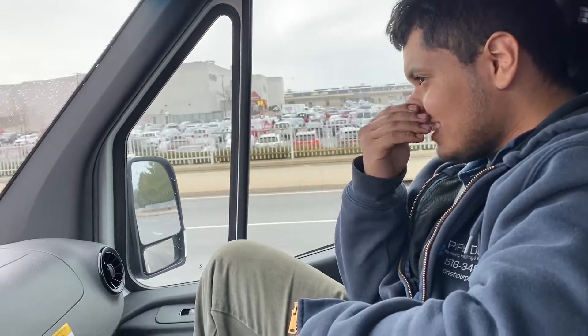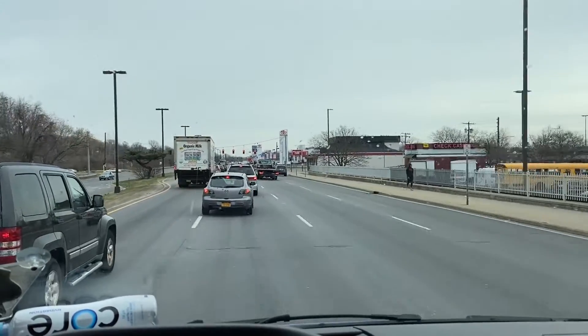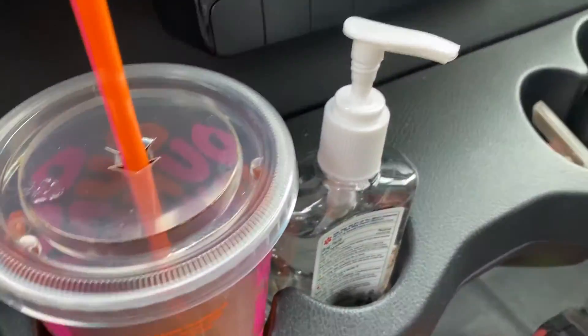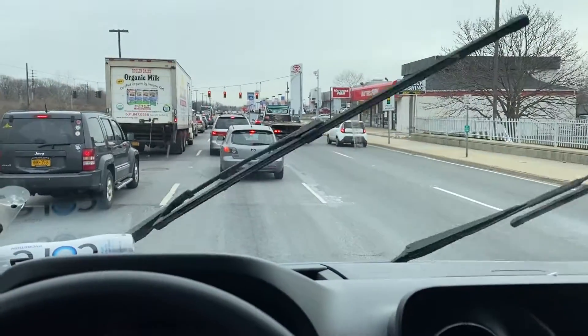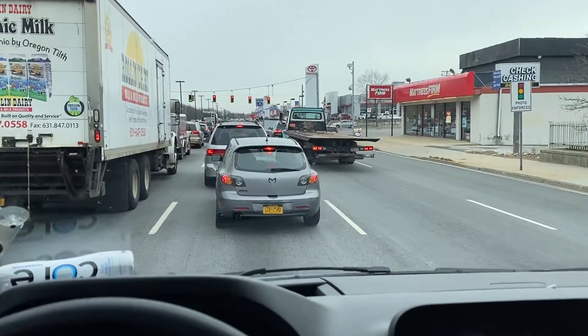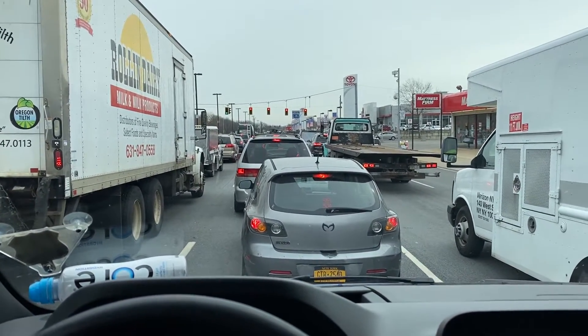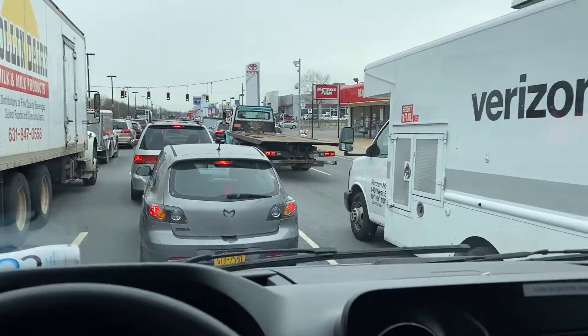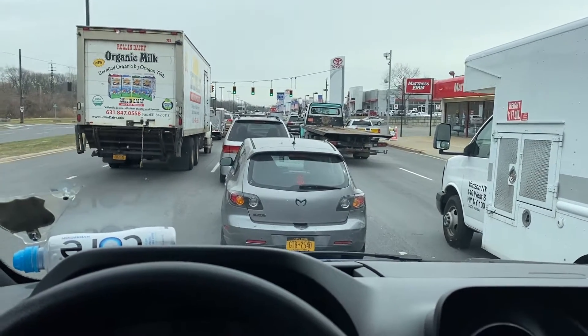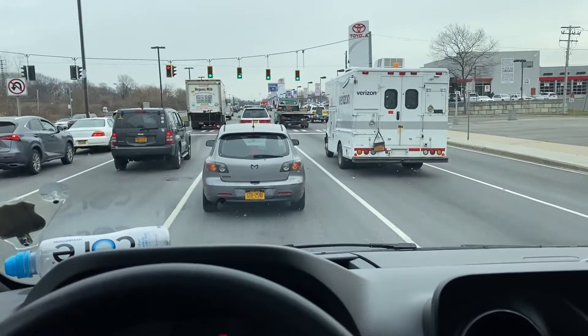Anyway Kelvin, you know where we're going now. We're going to a job where yesterday the guy's carbon monoxide detector was going off in his house, so the fire department came and turned off the boiler and the water heater and made the house safe. They called us — we've been there before a couple times. I think he's got a steam boiler, so we're going to go there, get our Testo personal carbon monoxide monitor going, get our Testo 320 going, and start up one by one and see what the problem is.